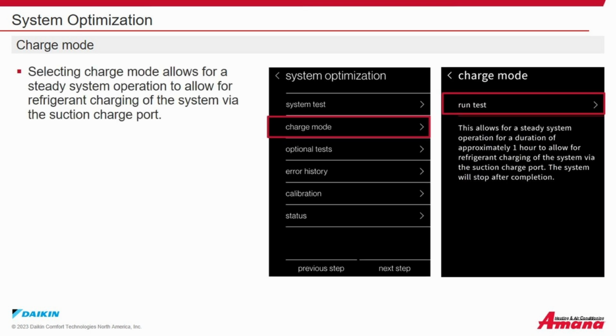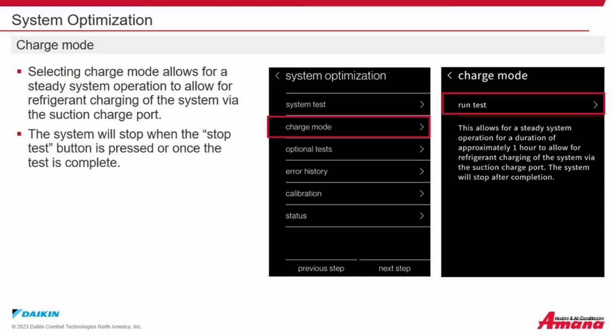Charge mode. Selecting charge mode allows for a steady system operation to allow for refrigerant charging of the system via the suction charge port. The system will stop when Stop Test button is pressed or once the test is complete. Note: for proper charging of the system, please see the equipment's installation manual.